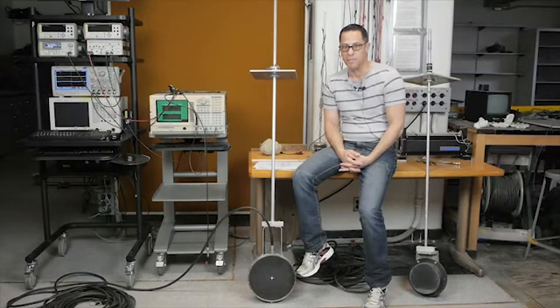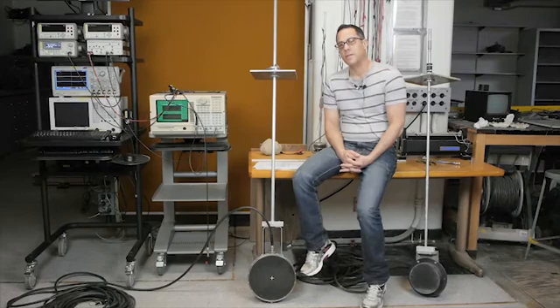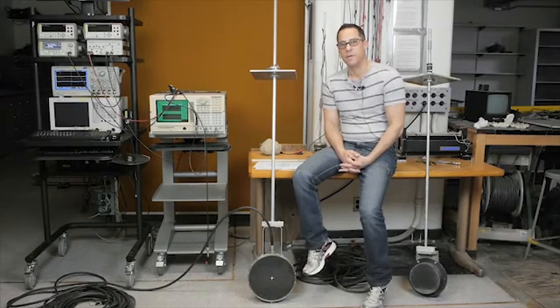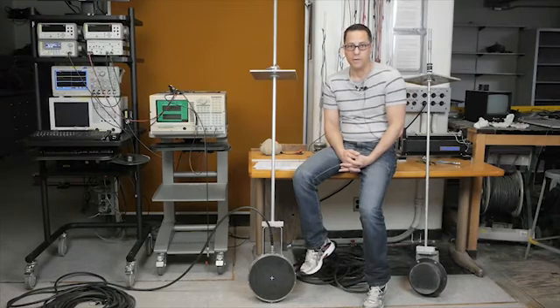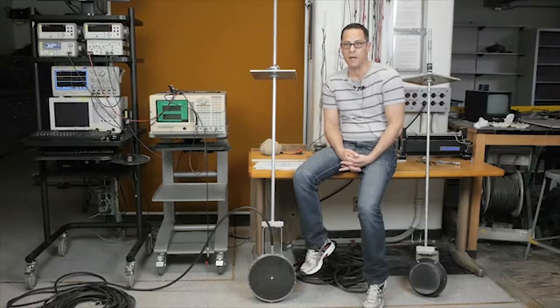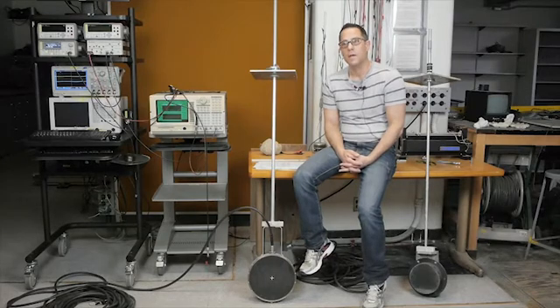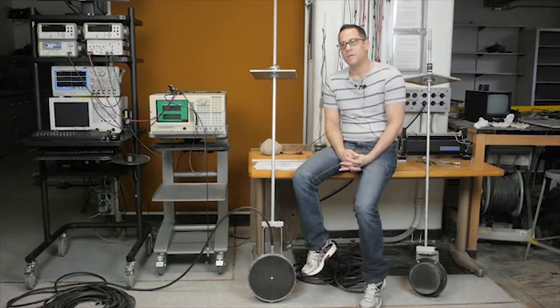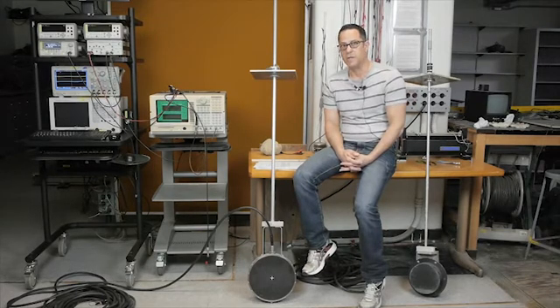the properties. Another common method of calibrating a hydrophone or microphone is the comparison method, where you take another hydrophone or microphone for which you have an absolute calibration, often supplied by the manufacturer, and then you compare your unknown transducer to the calibrated transducer. In this case, what happens if you don't have another calibrated transducer to compare it to? That's when you do reciprocity calibration.